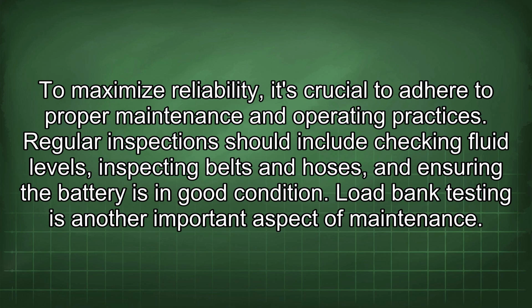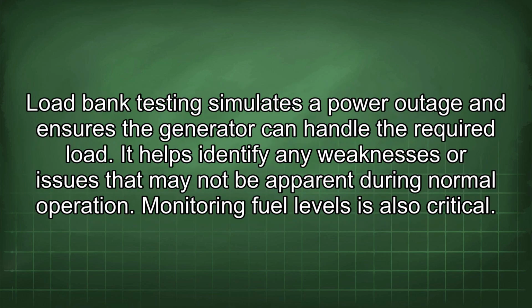Regular inspections should include checking fluid levels, inspecting belts and hoses, and ensuring the battery is in good condition. Load bank testing is another important aspect of maintenance. Load bank testing simulates a power outage and ensures the generator can handle the required load. It helps identify any weaknesses or issues that may not be apparent during normal operation.